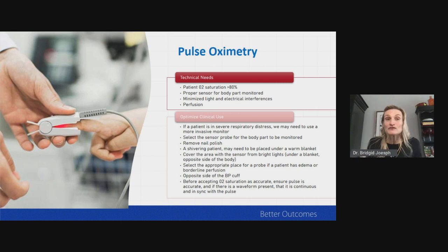It's going to give you a number. Is it accurate? Probably not. There are forehead probes for a reason, so if you need the forehead probe, use the forehead probe. If you need the nose probe, use the nose probe. Fingers for fingers. And slapping something on an earlobe, again, it might give you a number, but is it accurate? Most likely no. We've got to match what we should.